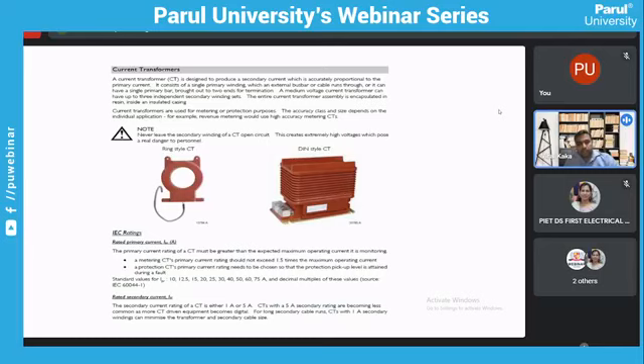CTs. Again, there are different types of CT arrangements and designs in which switchgears are developed. Normally, wherever you are using ring type CTs, these are all low voltage type CTs mounted on insulated bushings, which are connected to the lower jaw of the breaker. Ring type CTs are also possible to get and install on a medium voltage switchgear, but they come with a limitation of insulation, so that's where they are installed on an insulated bushing. Now, the figure on the right hand side is a wound type CT where physical bus bars from the cable compartments are connected and pass through the CT, so the short circuit or kA capacity of the CT also needs to be defined properly, because the bar is carrying that current through the CT itself.